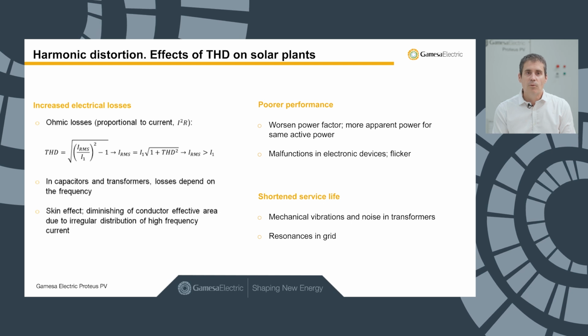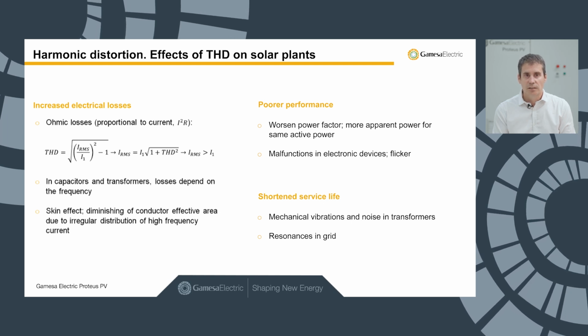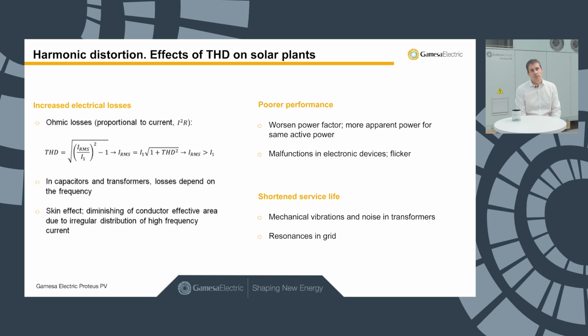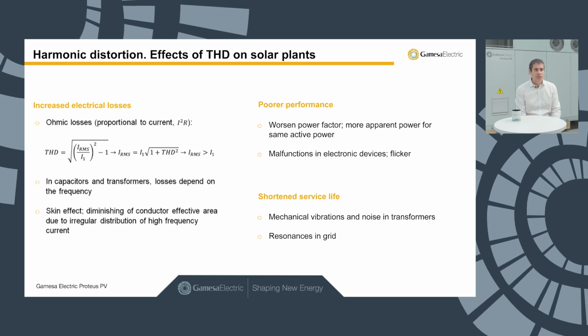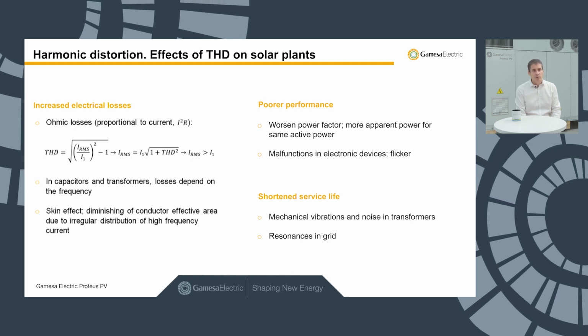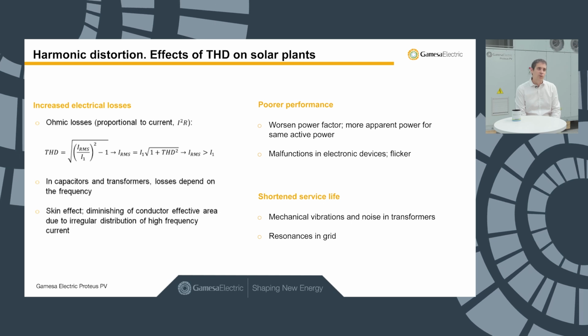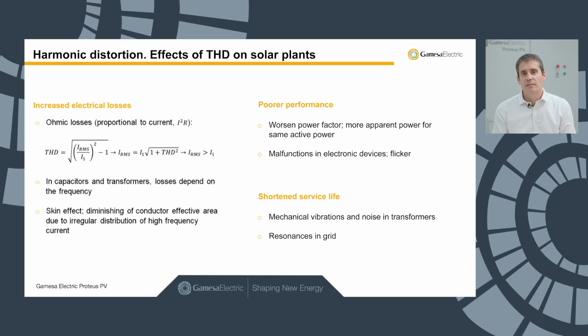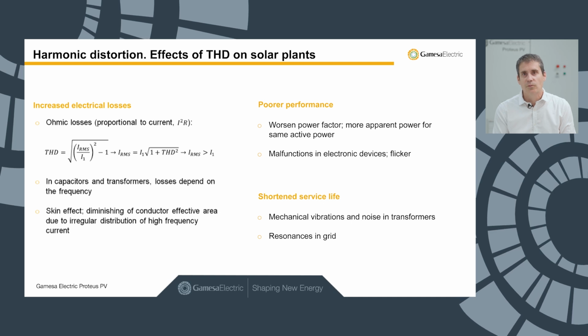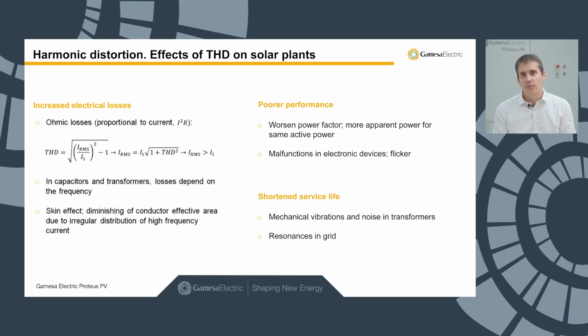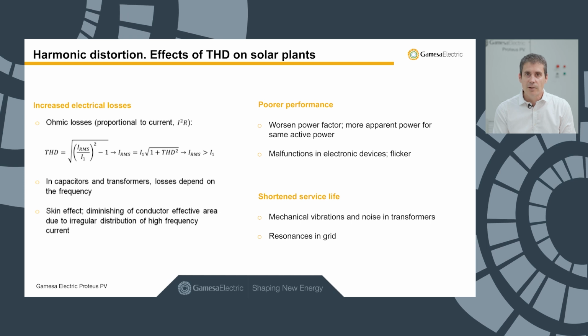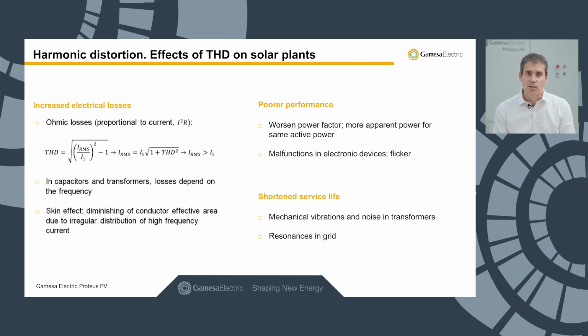And then we will see an effect of the THD. Moreover, we will have more electrical losses in the capacitors and transformers, depending on the frequency. And then we will also have a skin effect that will decrease the equivalent section of the conductors, due to the fact that current at high frequency only flows through the surface of the conductor.